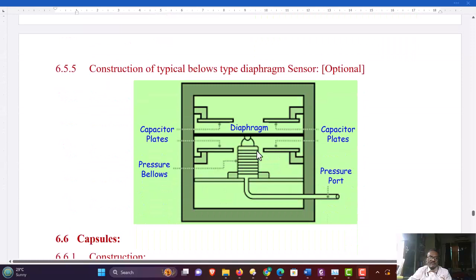A typical construction of a diaphragm type of sensor is shown in this figure. This is for additional information. Some sensors have this type of construction also. You will see there are two fixed plates of the capacitors. These are the fixed plates. In between the fixed plates, there is a metallic diaphragm plate stretched between the two rigid supports.